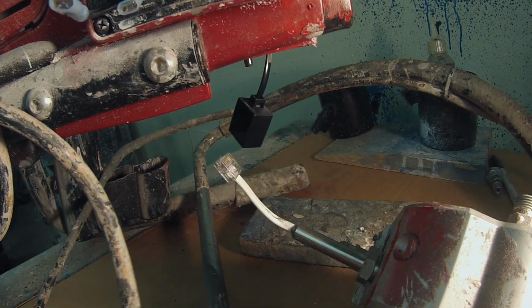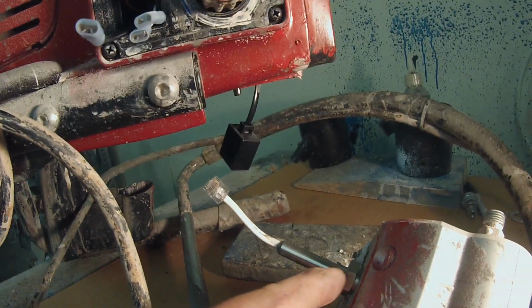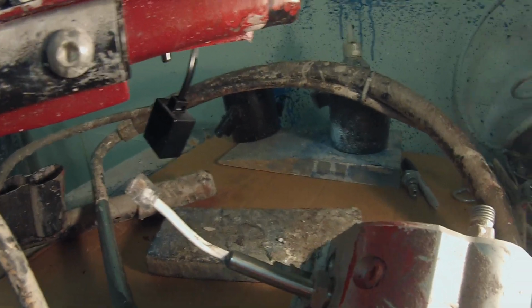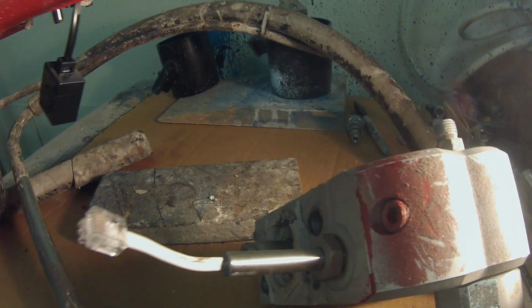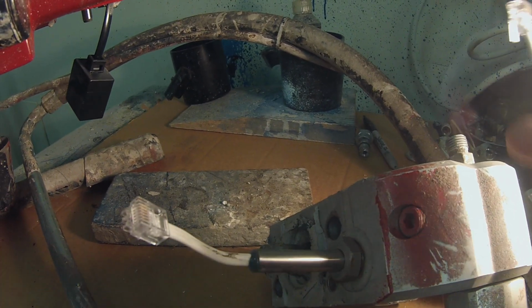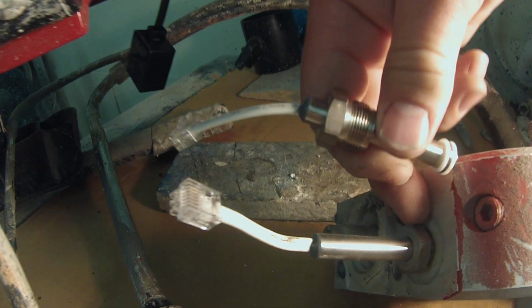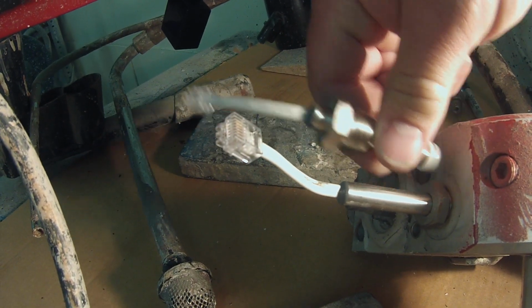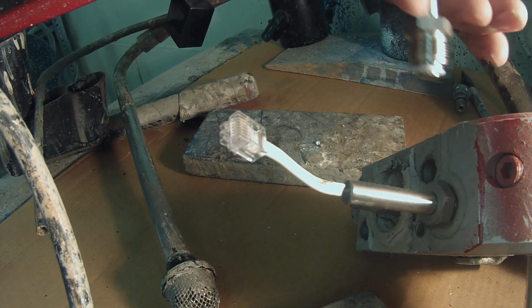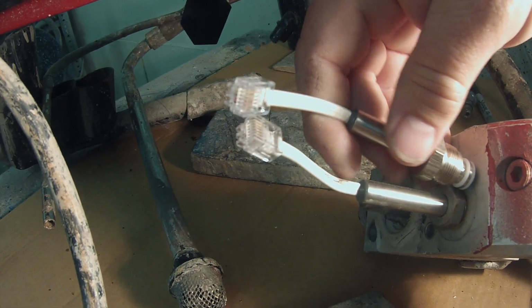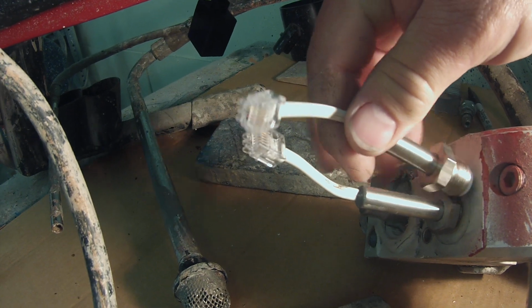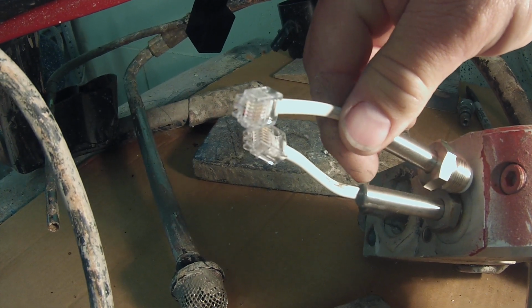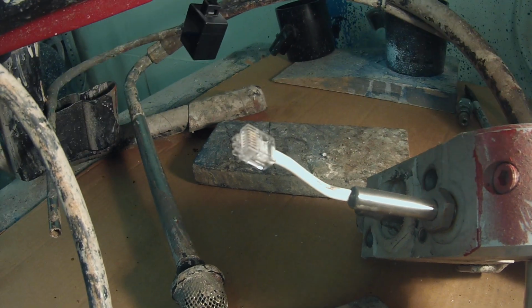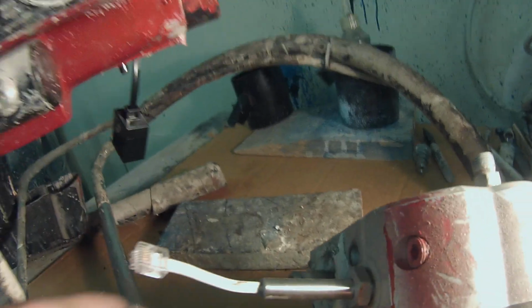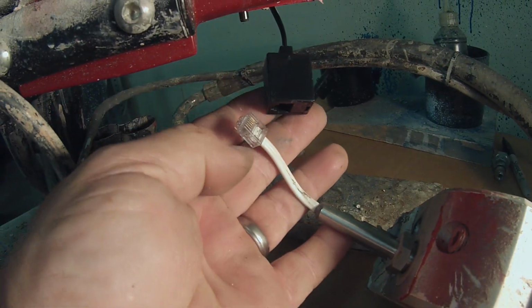Take your transducer loose. Again, just like on the Graco, you're going to take a 3/4 inch wrench and remove the transducer, same fashion. You're going to loosen it up, pull it out, slide the new one in, make sure the gasket comes out with it, so when you look in the end you'll see the white one. Slide the new one in, tighten it up by hand first, don't cross thread it. Once you've got it as tight as you can get it, then put the wrench on it and tighten it back up good and tight. You're going to plug your transducer back into the jumper.